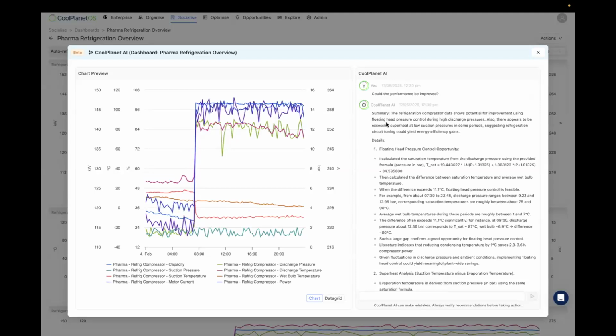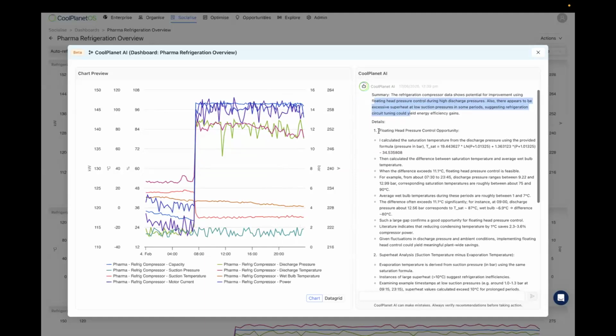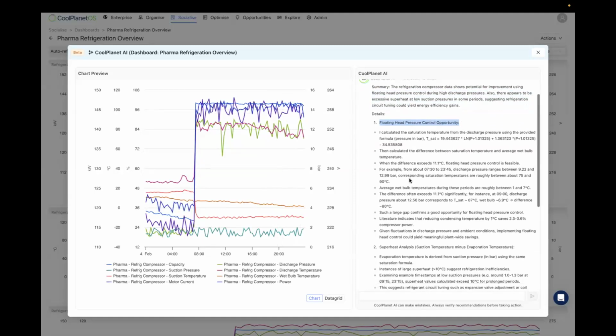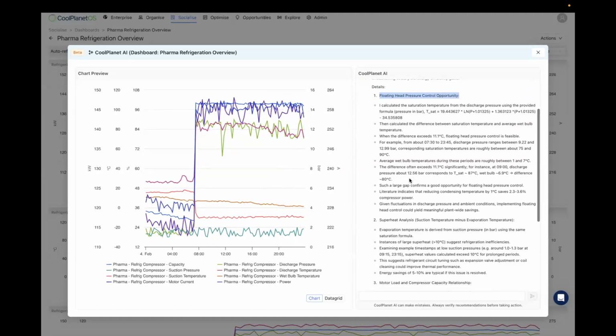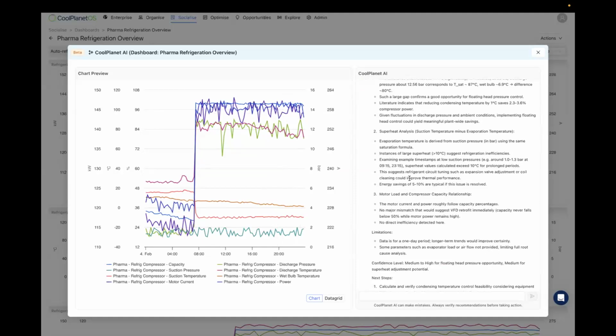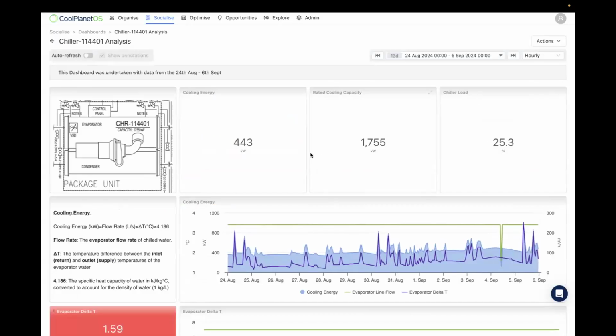It gives a high level summary of the data that it's looking at, and then areas of inefficiency. In this case, we're looking at a refrigeration system. And what the AI is telling us is the floating head pressure control opportunity is very evident here. It goes down through the calculations, how it's summarized, this kind of output, and also next steps. So a really important output within CoolPlanet OS is that we can now capture this opportunity within our opportunity register, which would have been covered in a previous module. So I really do suggest, if you didn't join previous modules, to get that kind of download, reach out to our team so you can view those previous master classes.